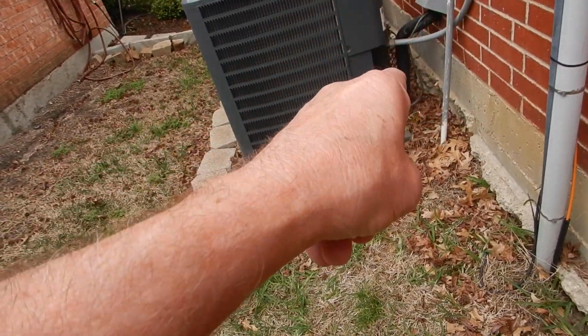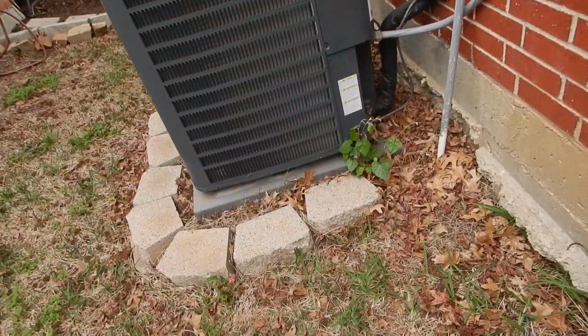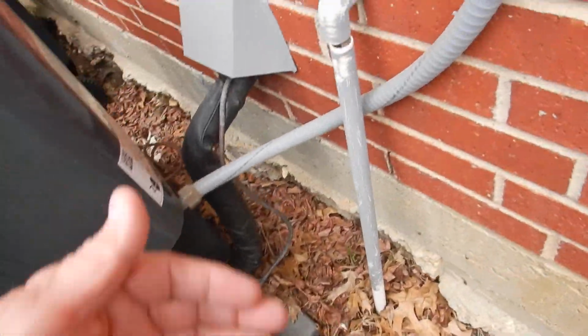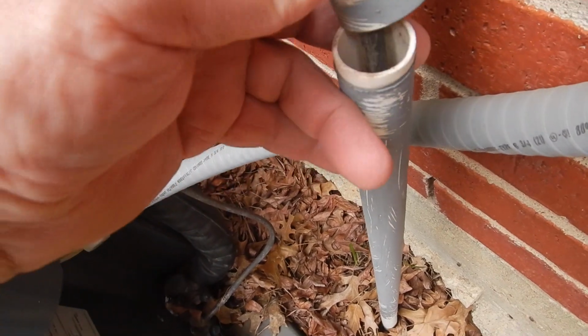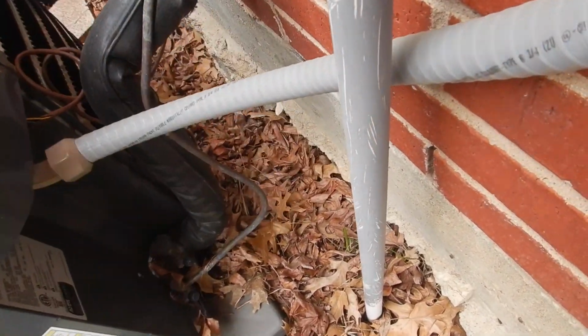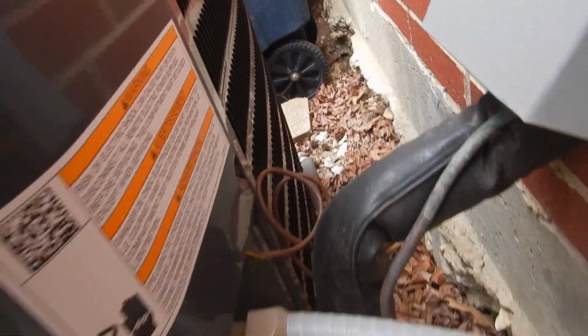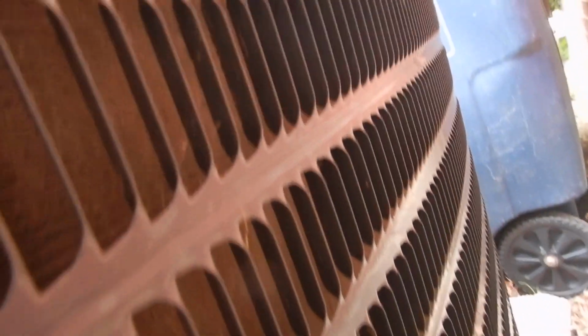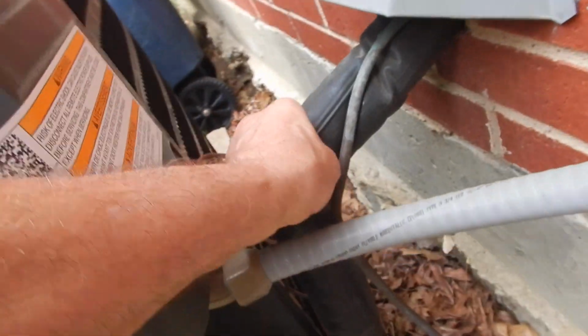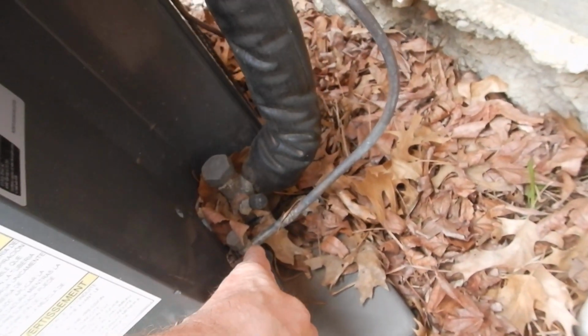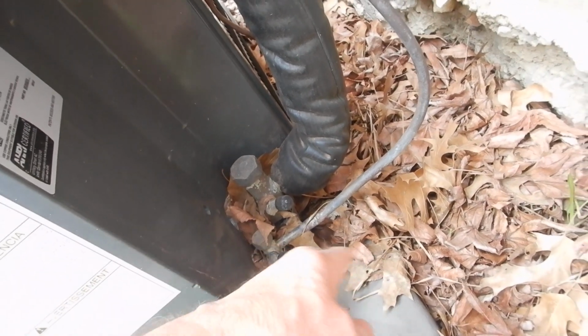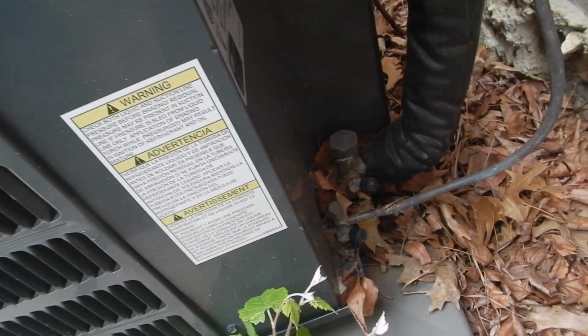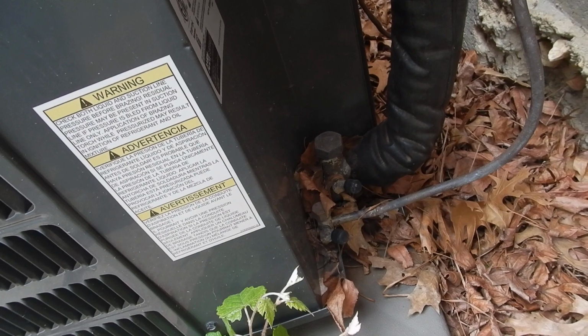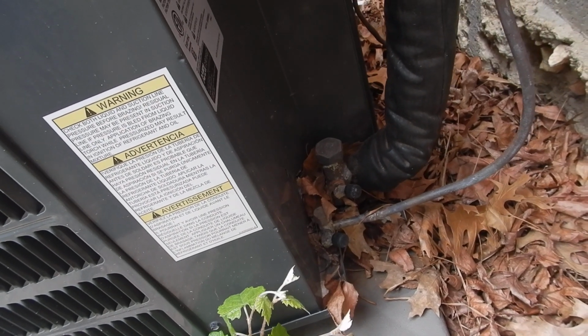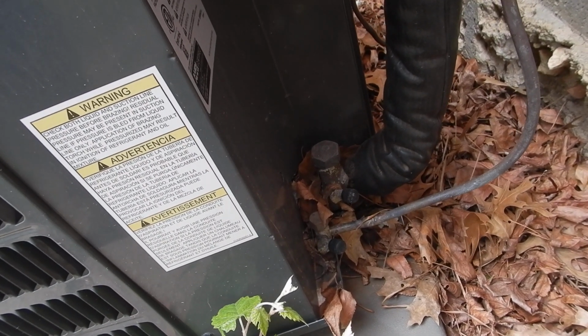Now our refrigerant piping is properly sealed, and we got a nice draft hood over here. I like this. This is the lawn sprinkler system. You think water can get off and down in there in your electrical? I do. Over here, we're looking at dirty coils. This is a nice robust refrigerant piping system, but our Schrader valves, look that up in the dictionary, you won't, but our refrigerant piping service valve port caps should have been anti-theft. They should have been anti-theft.